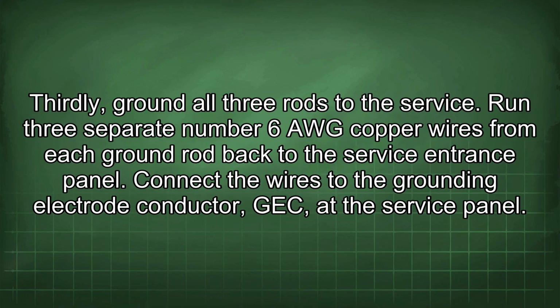Thirdly, ground all 3 rods to the service. Run 3 separate number 6 AWG copper wires from each ground rod back to the service entrance panel. Connect the wires to the grounding electrode conductor, GEC, at the service panel.